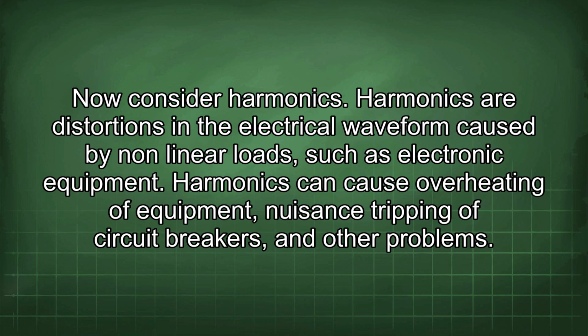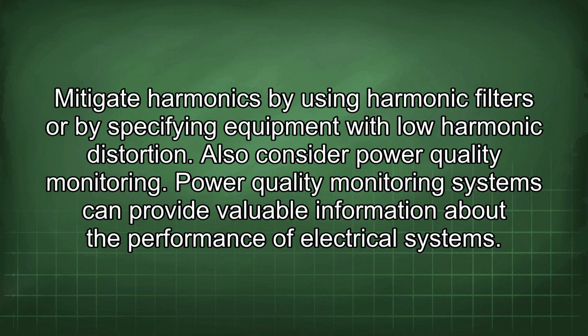Now consider harmonics. Harmonics are distortions in the electrical waveform caused by nonlinear loads, such as electronic equipment. Harmonics can cause overheating of equipment, nuisance tripping of circuit breakers, and other problems. Mitigate harmonics by using harmonic filters or by specifying equipment with low harmonic distortion.